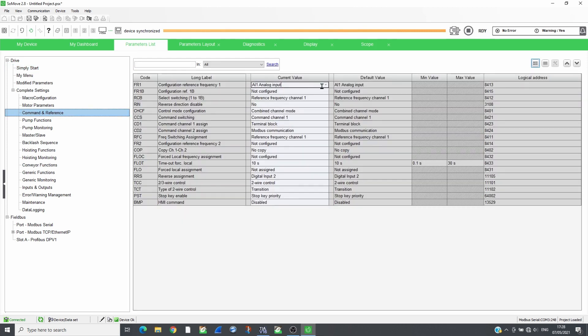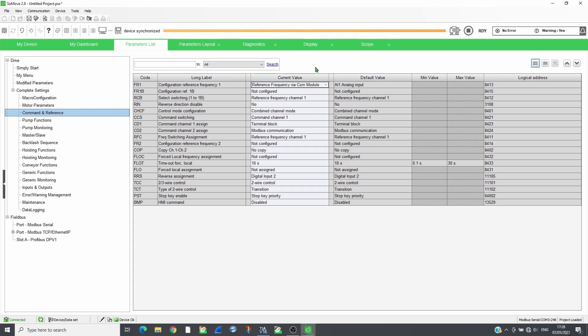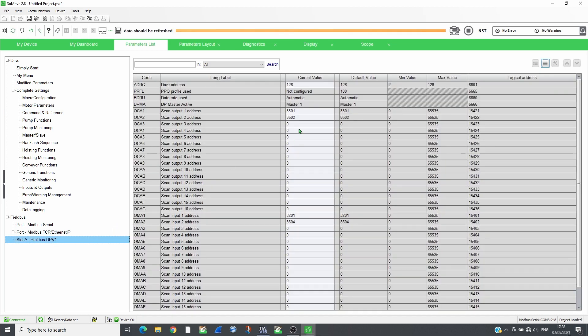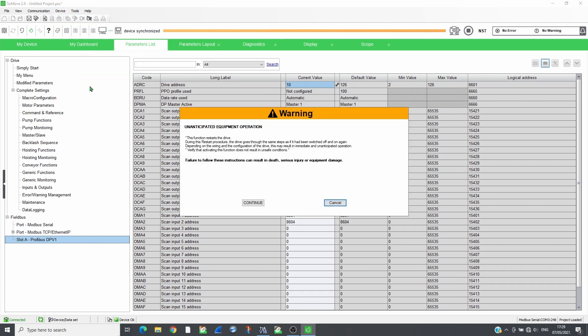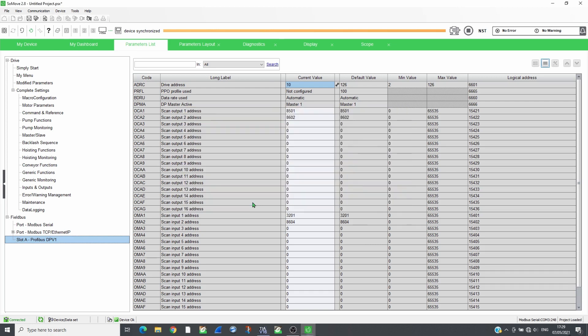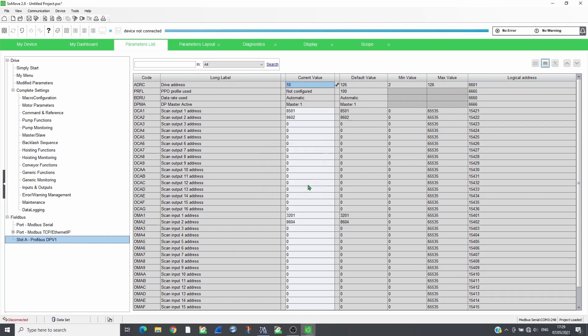The drive will be controlled following the CIA402 profile. Set the PROFIBUS address and apply the changes, then restart the drive. Connect again to the drive and check that the parameters are saved.